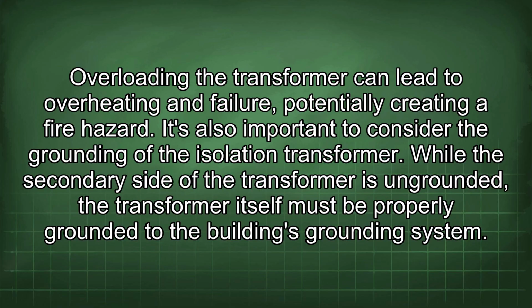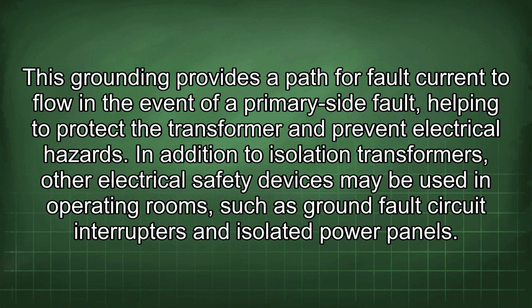It's also important to consider the grounding of the isolation transformer. While the secondary side of the transformer is ungrounded, the transformer itself must be properly grounded to the building's grounding system. This grounding provides a path for fault current to flow in the event of a primary side fault, helping to protect the transformer and prevent electrical hazards.